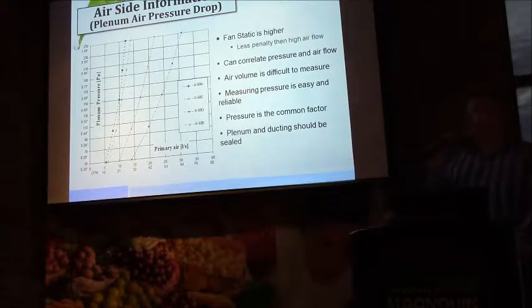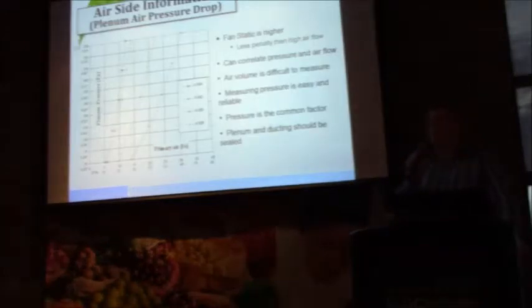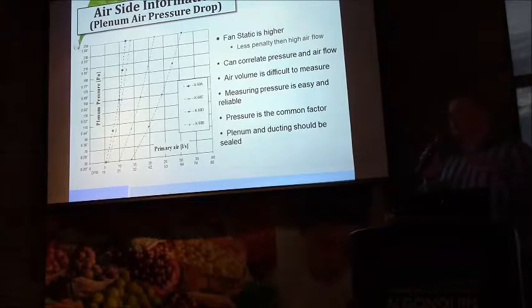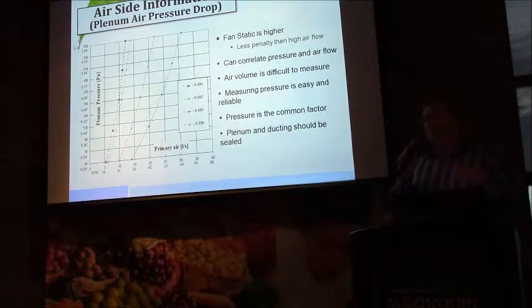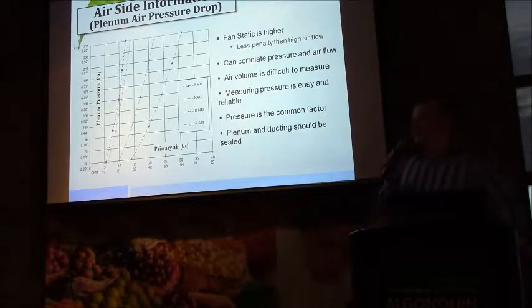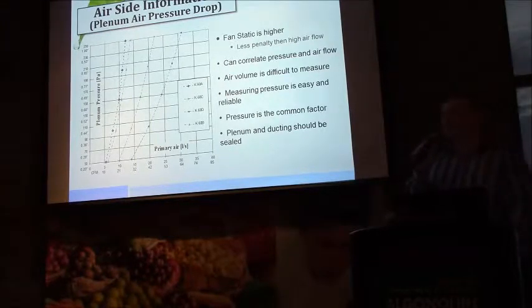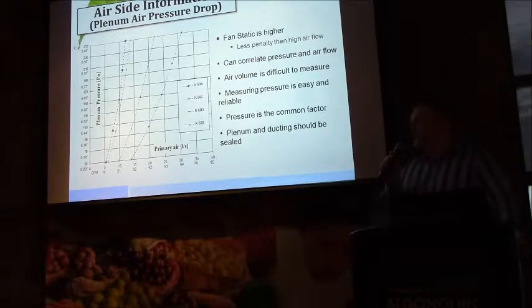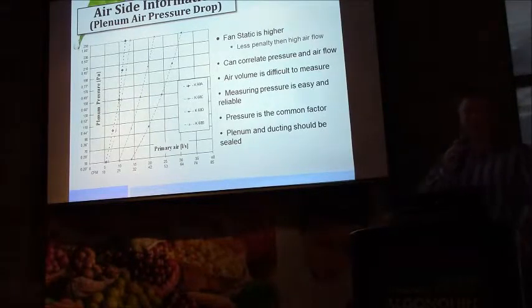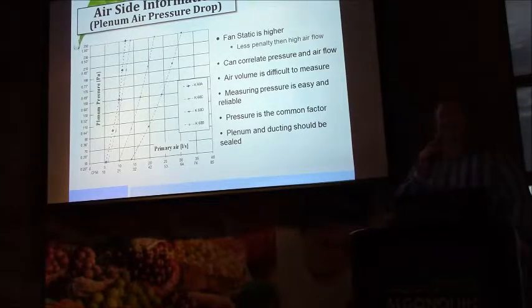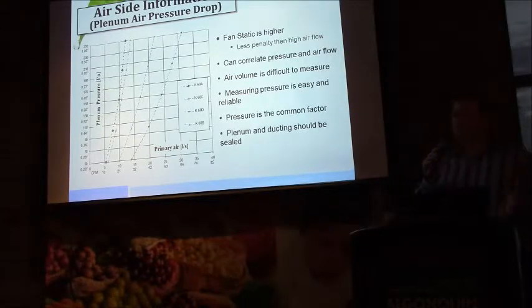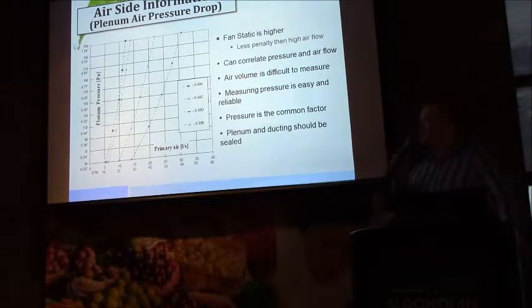The weakness or the pitfall of designing an active beam system to the minimum plenum static pressure is that we have no low side for churn in the space. So the lower limit of the plenum static pressure to the beam is really governed by our ability to create a pattern in the space. To create Coanda effect or throw and drop into the space, generally beams will bottom out in the neighborhood of about 0.3 inches. And so if our system design is arranged around all beams that are scheduled for, say, 0.3 inches, give or take, we now have no opportunity to lower the capacity in that space in the event that the loads change or the space sees churn. And so oftentimes we'll advocate for plenum static pressures that are somewhere more in the middle of the range.